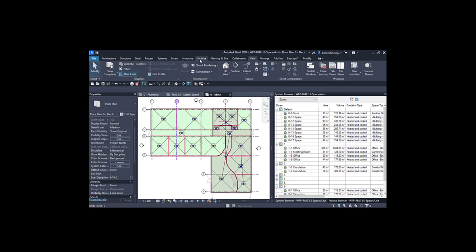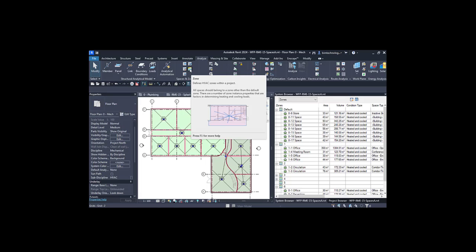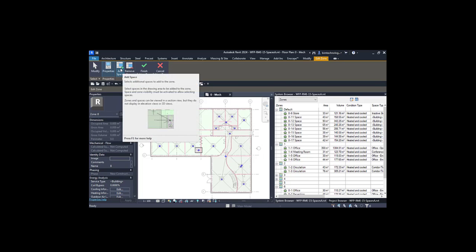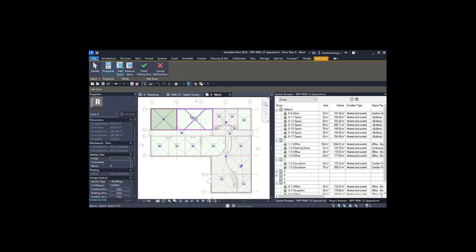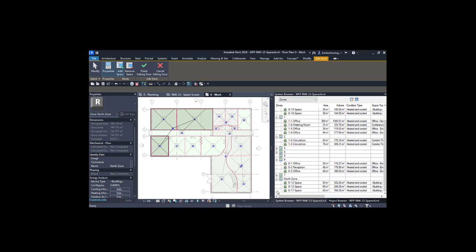Now let's see how to add zones. Go to the Analyze tab and in Spaces and Zones, you have the Zone option. The moment you click the Zone tool, the Edit Zone contextual tab is displayed. Click the Add Space button and select the spaces you want to add — three spaces are added to the zone. You can name the zone, and once added, it appears in the system browser with spaces 12, 13, and 17 along with their areas and parameters.